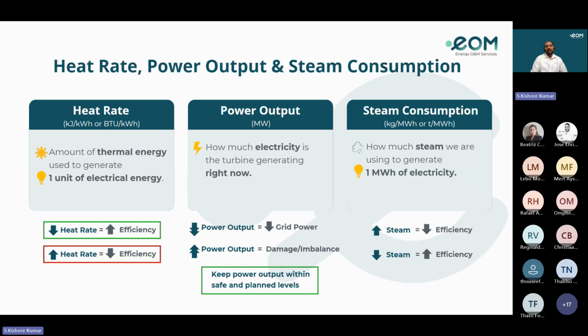For example, a good turbine might use 5 tons of steam per megawatt. If it starts using 6 tons per megawatt, something is wrong, maybe fouling because of wear or poor steam quality. In some turbines, it takes more or less 3.9 to 4.5 tons per megawatt. Based on the turbine, it may vary. So our goal is to reduce the steam consumption per unit of power to boost efficiency and save fuel.